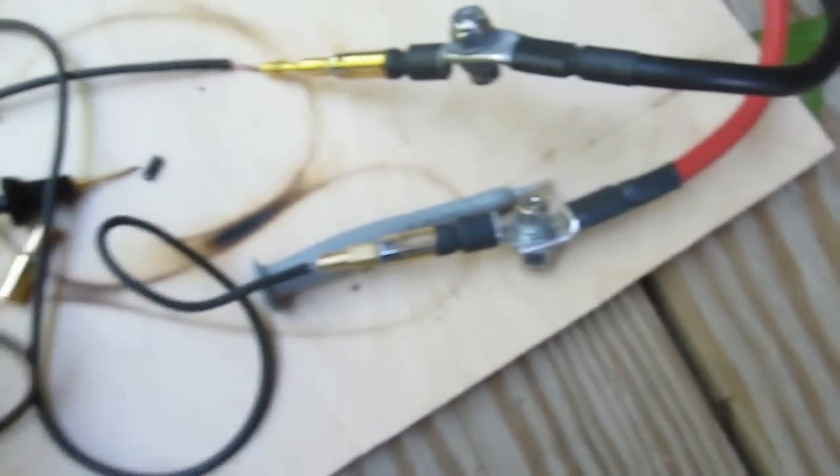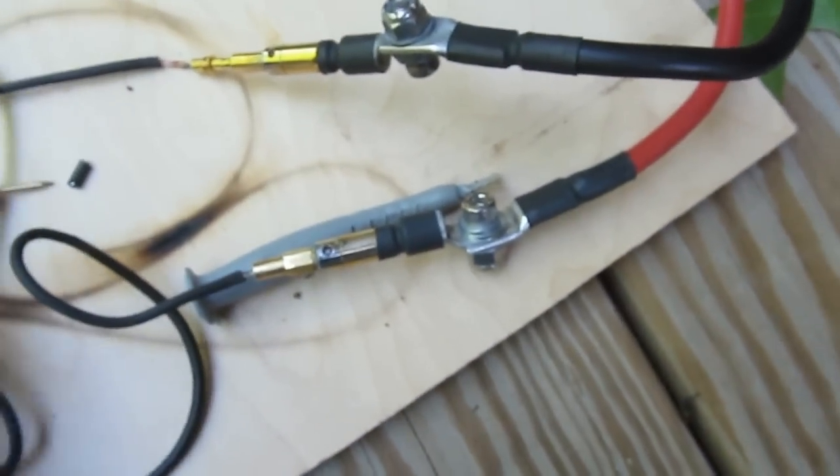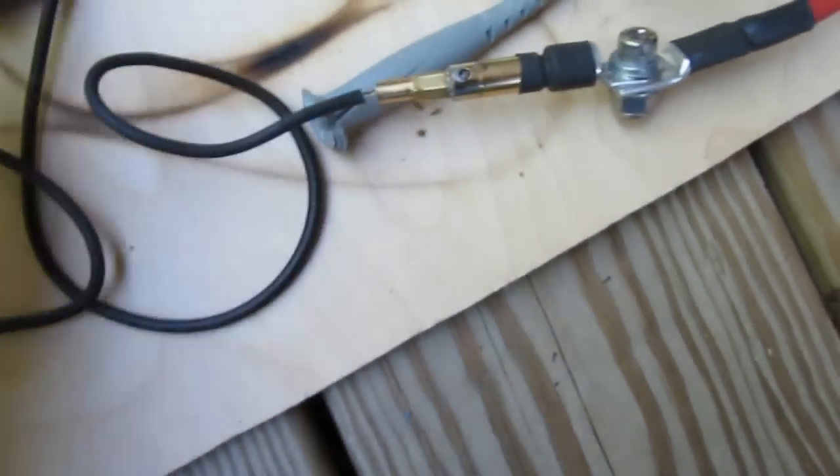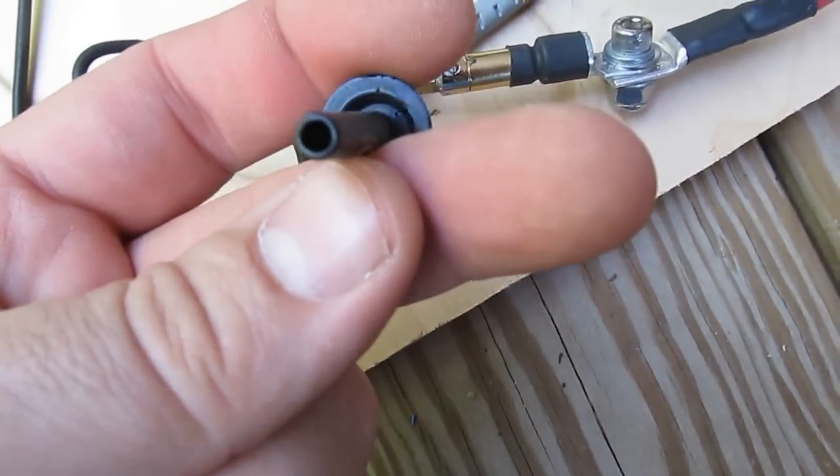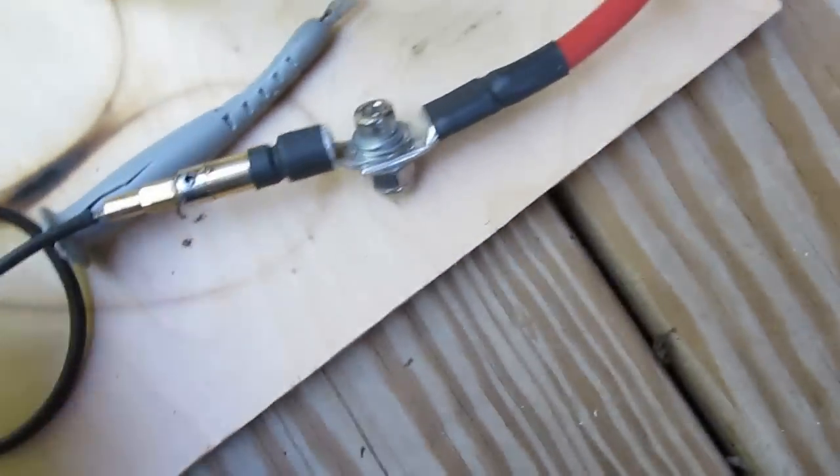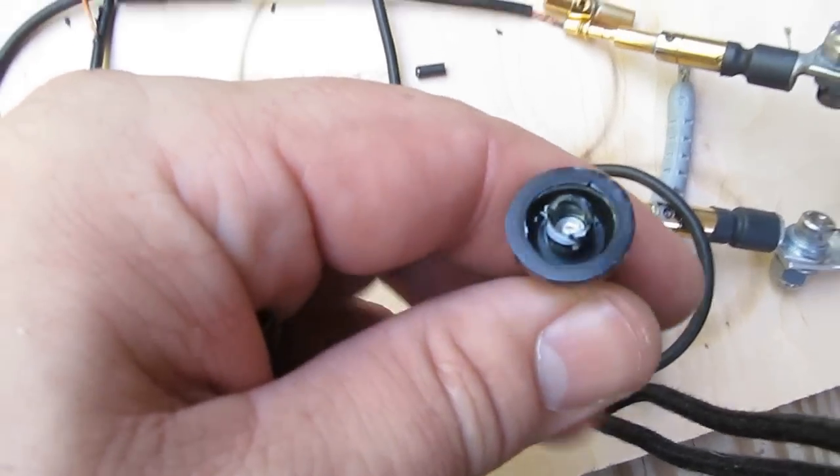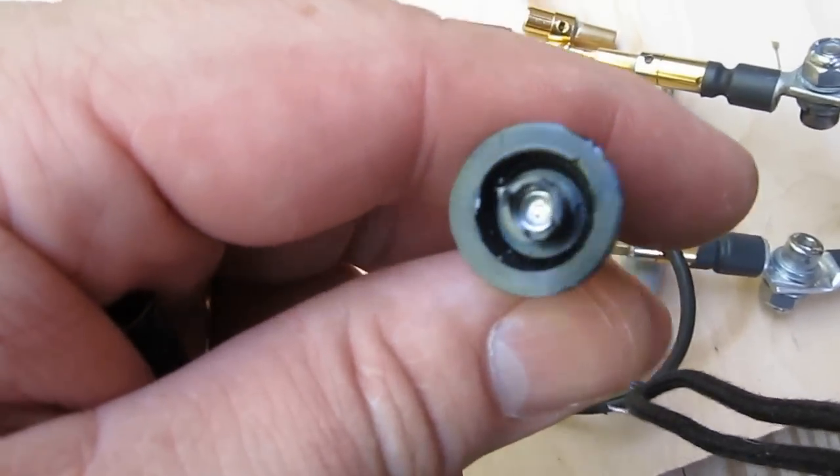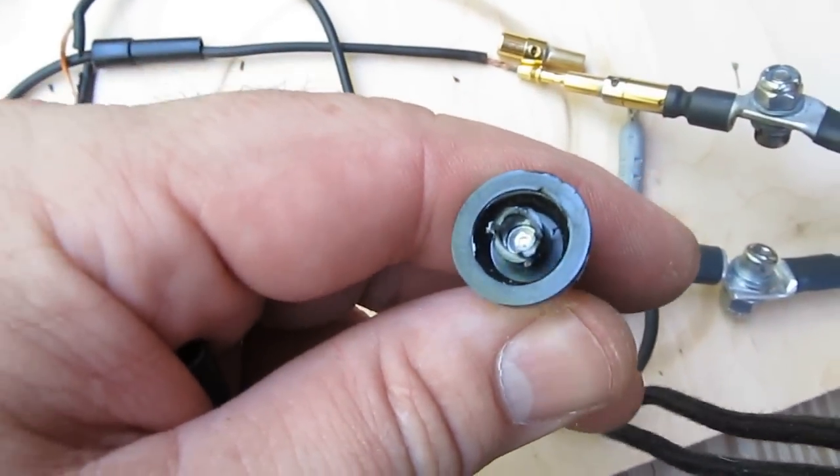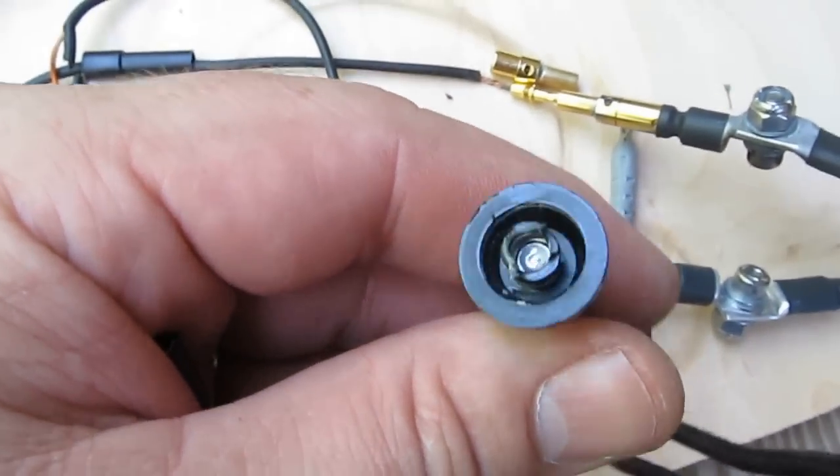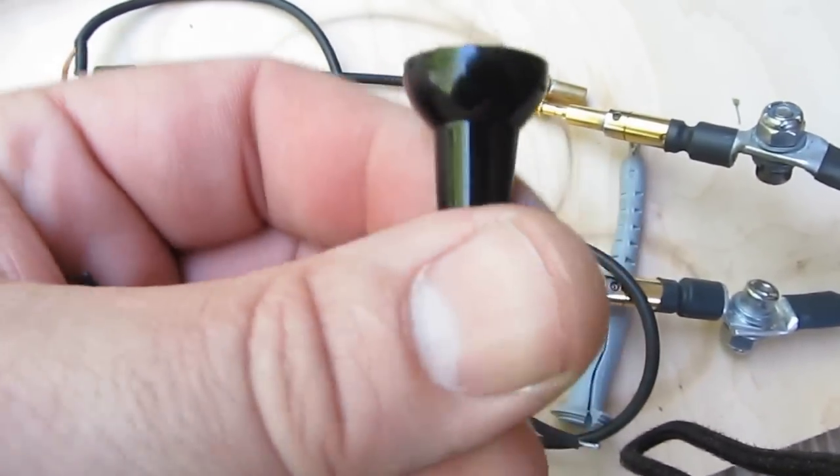So I took this thing apart. The wire looks in very good condition. It looks like what actually happened is down inside of the probe, the solder joint had failed. You can see it just solders down inside and that got so hot, it just became unsoldered.